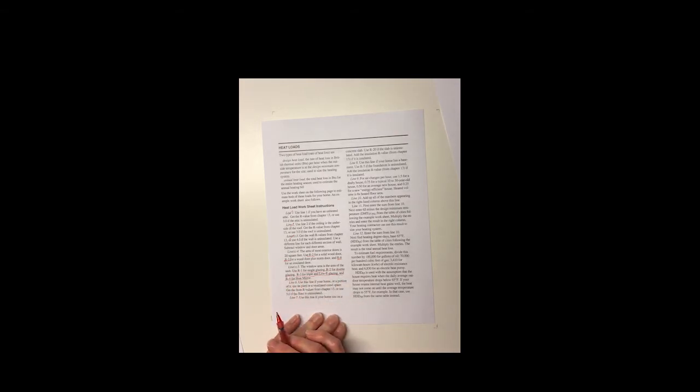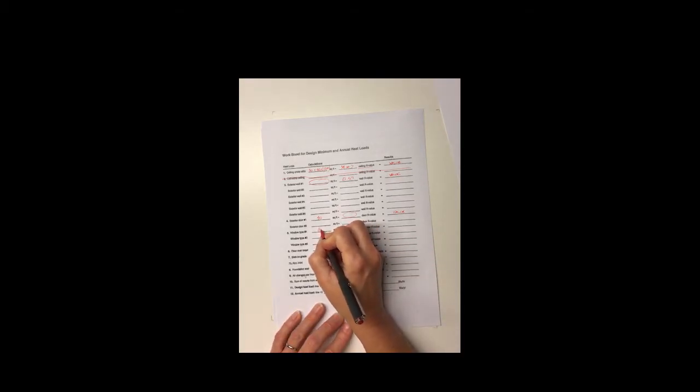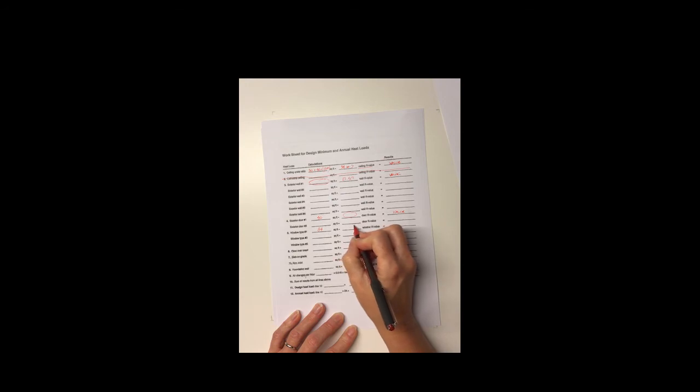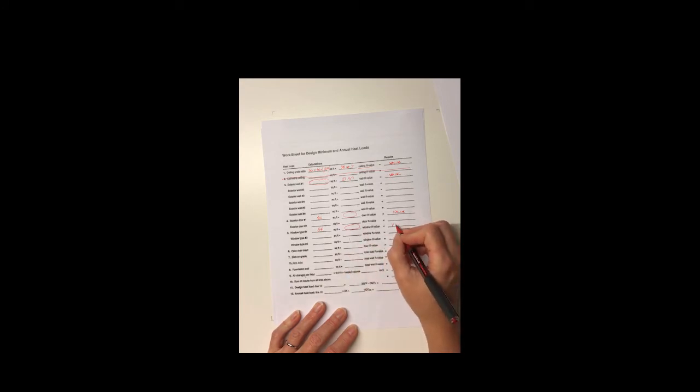And so most residential projects are double glazed windows, so I would use an R2, but technically you could use any one of those. So we know in this case we're just using all of the windows as the same window type, so we would have 84 square feet, and then whichever R value you select, and then you take that 84, divide by that value, and then we're going to get what our total is here.